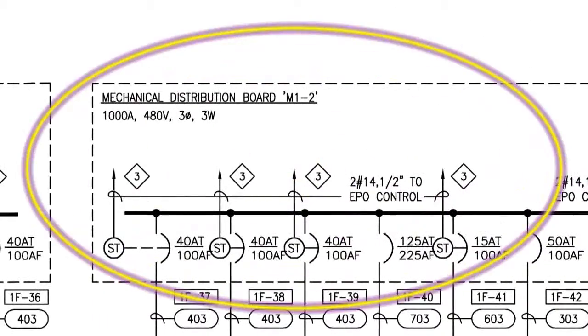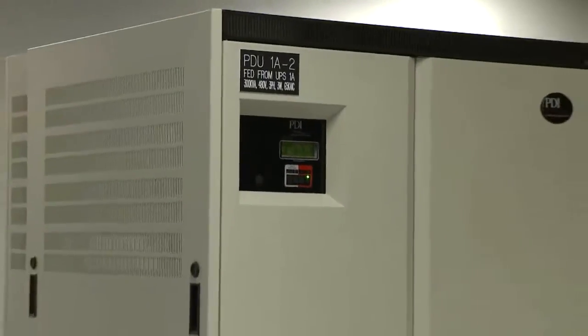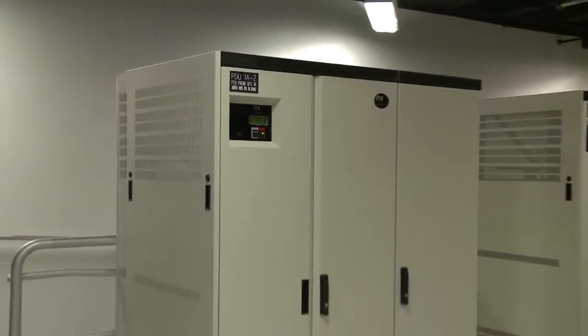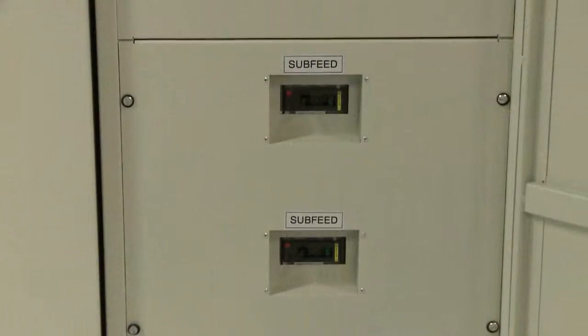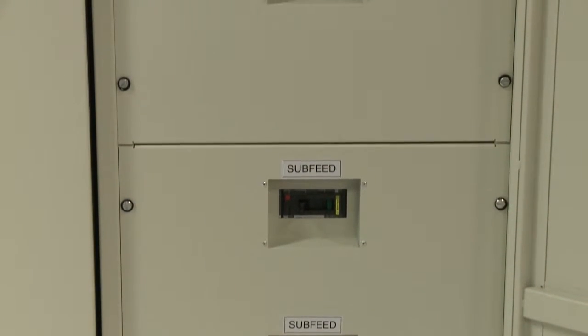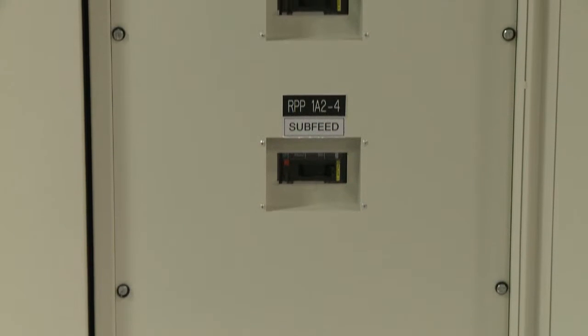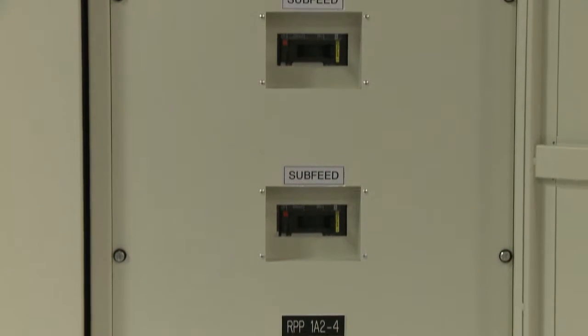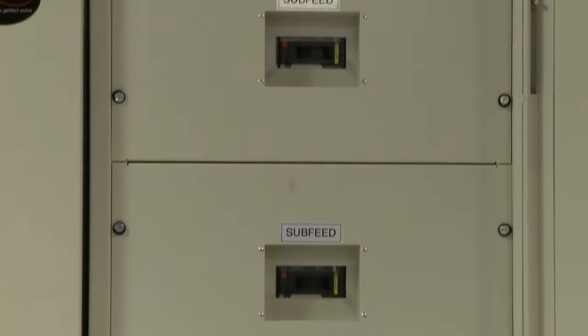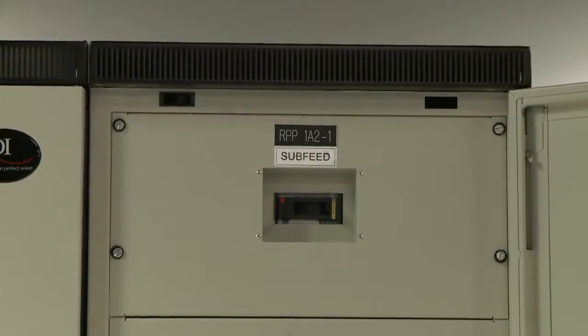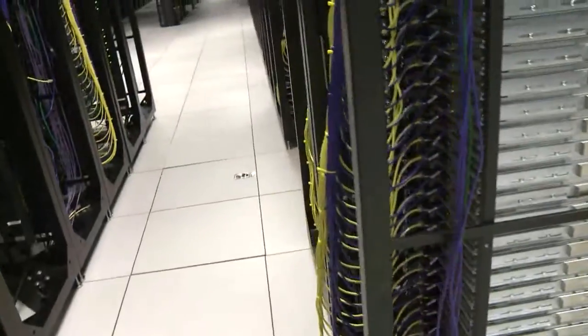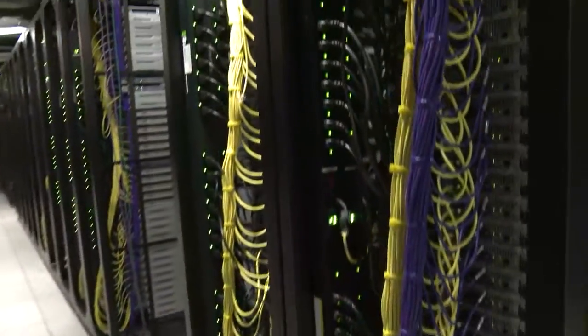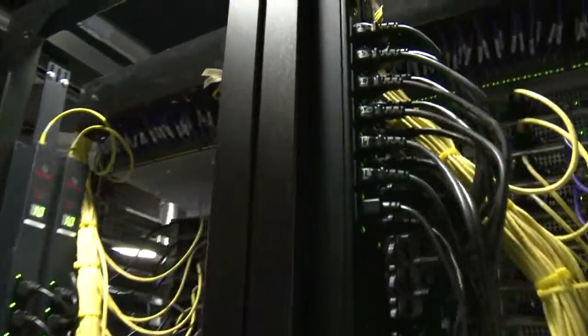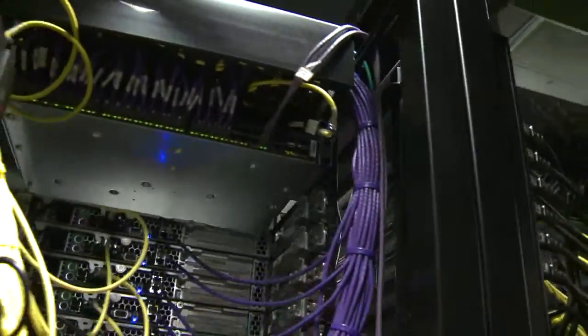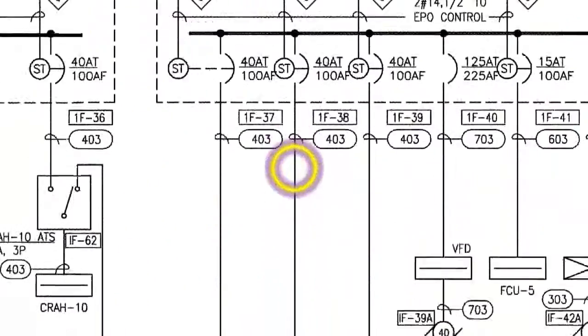A power distribution unit, or PDU, transforms power from 480 volts to 120/208 for distribution to the remote power panels, or RPPs. This system consists of a step-down transformer and numerous distribution breakers. The individual 30-amp breakers provide power to the boot boxes located at the cabinet level. From there, the servers are plugged in to provide power to each server. Each boot box is managed and redundancy is maintained.